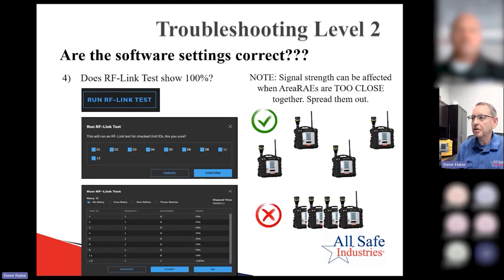Once you've started the PTM protocol, click on the RF link test button. It will prompt you to confirm the next window showing the unit IDs it's getting ready to test, and you'll also need to click the start button at the bottom of this window. Once you click start, it sends a ping to the instrument, waits for the area RAE to respond, and gives you the percentage of pings that responded during the test. When that's complete, click OK on the test window, then simply X out of the Run RF Link Test screen.